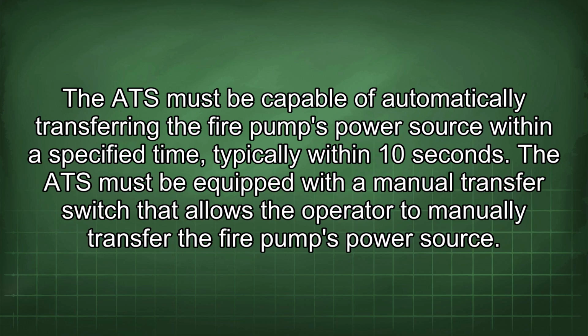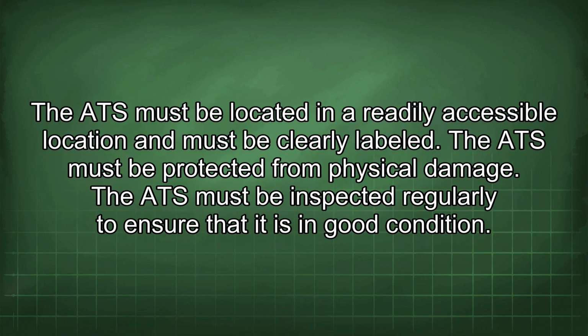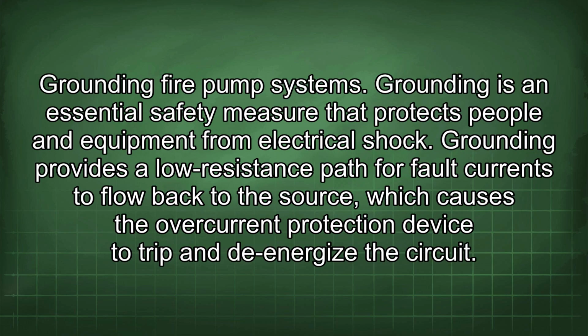The ATS must be equipped with a manual transfer switch that allows the operator to manually transfer the fire pump's power source. The ATS must be located in a readily accessible location and must be clearly labeled. The ATS must be protected from physical damage. The ATS must be inspected regularly to ensure that it is in good condition. Grounding fire pump systems. Grounding is an essential safety measure that protects people and equipment from electrical shock. Grounding provides a low resistance path for fault currents to flow back to the source, which causes the overcurrent protection device to trip and de-energize the circuit.